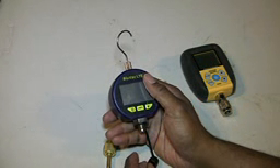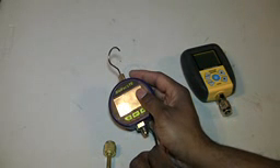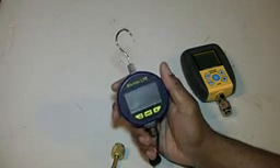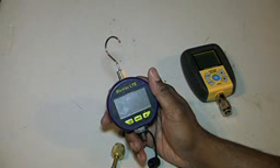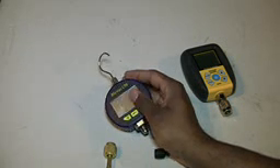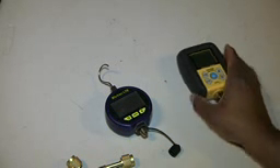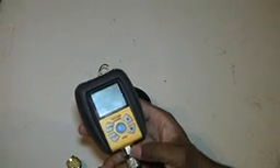When I first started using it, I was using it with my Appion half-inch hoses and my Appion core removal tools, and I couldn't get this micron gauge to register. For weeks on end when I would try to use it, it wasn't working out, and then I had to go back to using the built-in micron gauge on my S-Man 4.